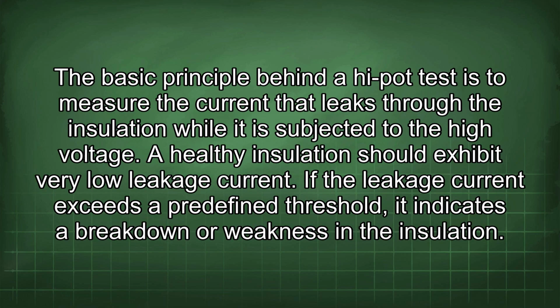The basic principle behind a high-pot test is to measure the current that leaks through the insulation while it is subjected to the high voltage. A healthy insulation should exhibit very low leakage current. If the leakage current exceeds a predefined threshold, it indicates a breakdown or weakness in the insulation.